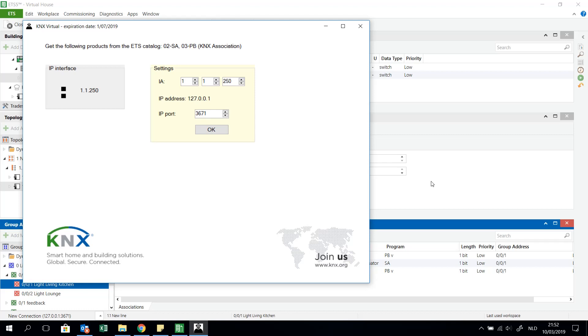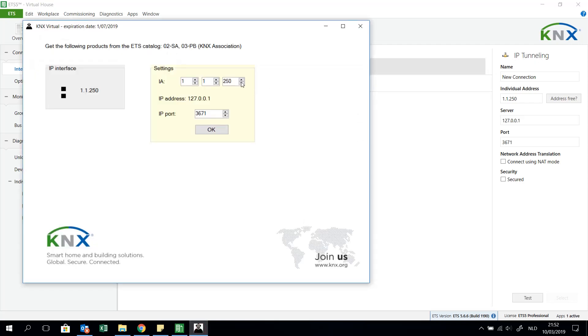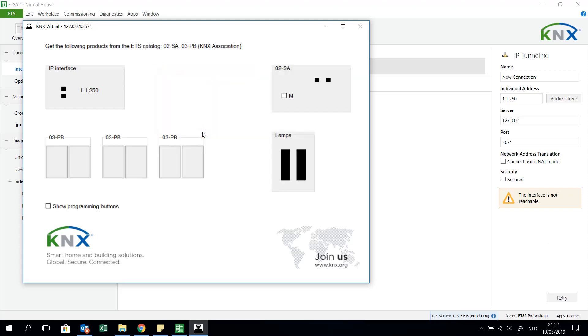The most important thing is how I can simulate this virtually and download my program to those virtual components. It is very important that for my IP interface settings, I take these IP interface settings. I go to bus and I see a new IP tunneling interface. I will take over these settings: individual address 1.1.250, IP address 127.0.0.1, and port 3671. So then I have to start this and click OK. I see my interface — I see the possibility to have 1, 2, 3 push button interfaces, but with the same application software.